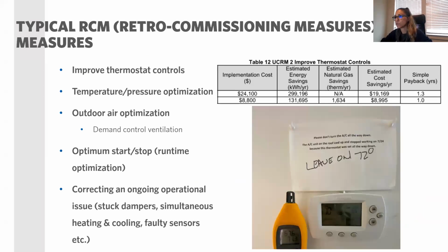So, as I mentioned, we categorize RCM versus ECM, but sometimes this could be interchanging based on the utility structure or existing operation and some other factors. Sometimes an LED replacement actually could be a RCM based on the simple payback period. So as a rule of thumb, though, we consider any measure with a simple payback period of less than 1 year a low cost measure. And typically these are the control related measures.